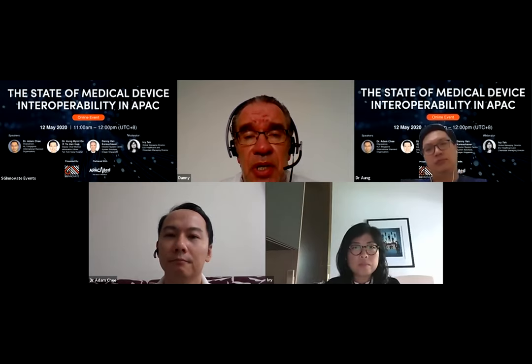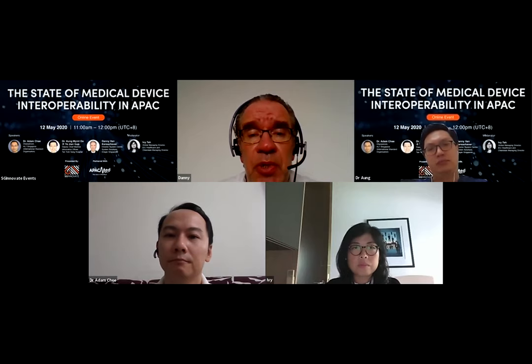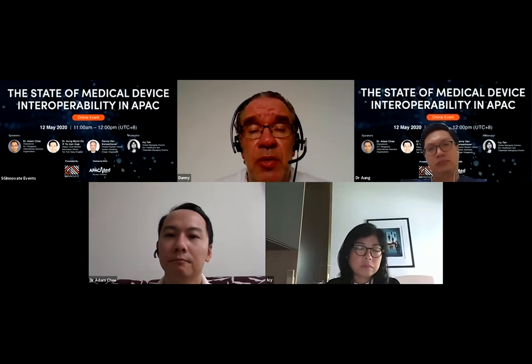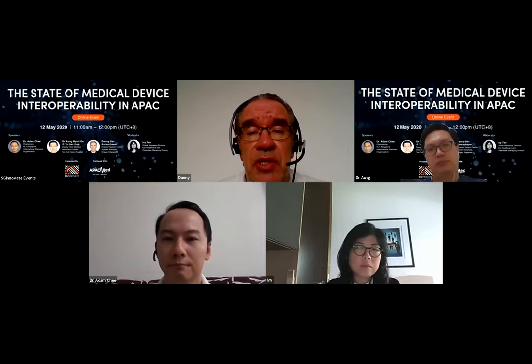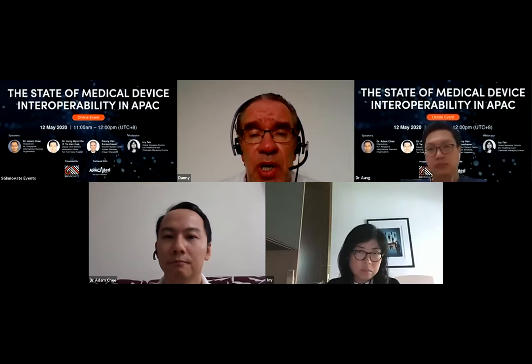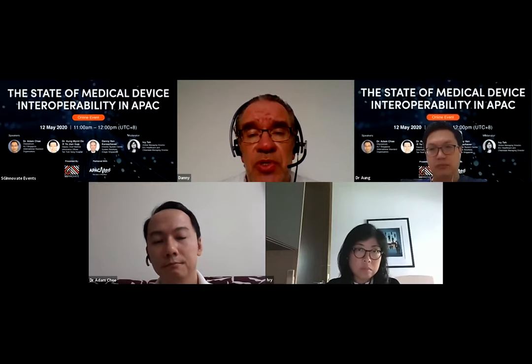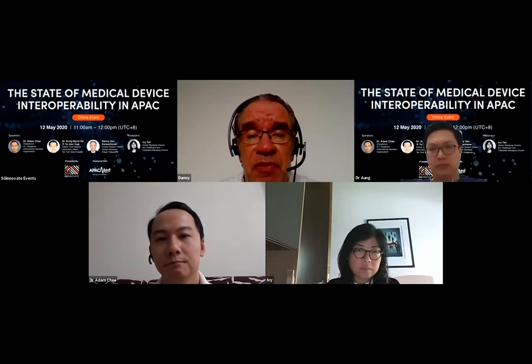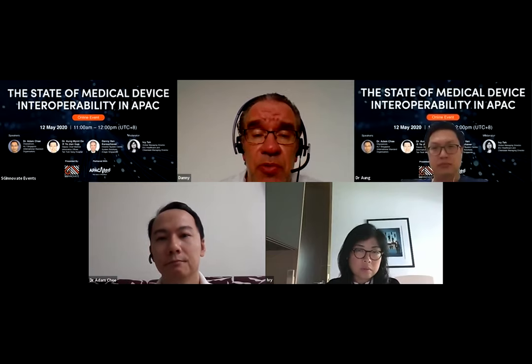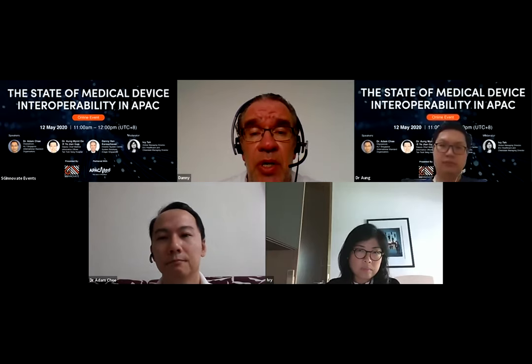So the alarms will only sound inside the isolation room where the patient is, not always where the caregiver is. If we can distribute these alarms outside the isolation room to the nurse and caregiver, it will be safer for the patient, and at the same time reduce alarm fatigue for the patient itself. It will be more comfortable for the patient not to have all the alarms beside him, because he doesn't need to know if a device is going into alarm. It's the caregiver who should be aware of alarms.